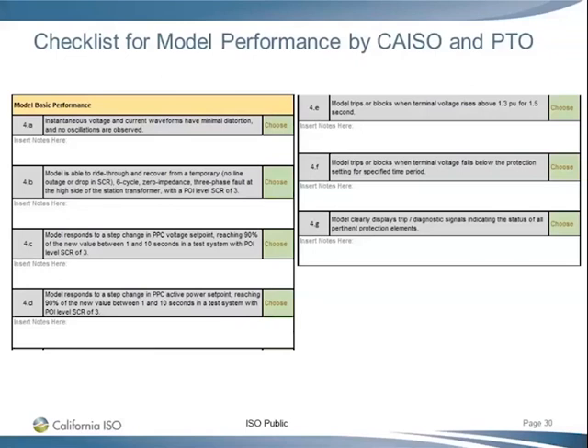There's a question: do you have any requirement on momentary cessation? So we have momentary cessation as an interconnection requirement. This is for modeling. So we just want you to show if the generator, the inverters do momentary cessation, it should be reflected in the model. So that's why we want you to list all the protection that includes momentary cessation, and we will try to verify that. We probably don't have a particular task on this checklist to verify momentary cessation. That's something we can consider adding to the checklist.